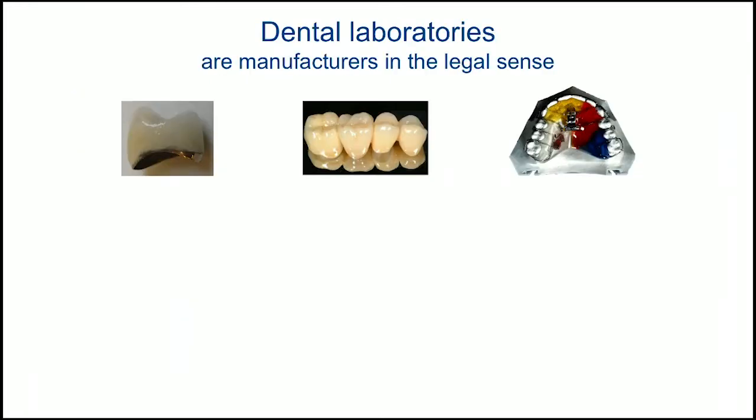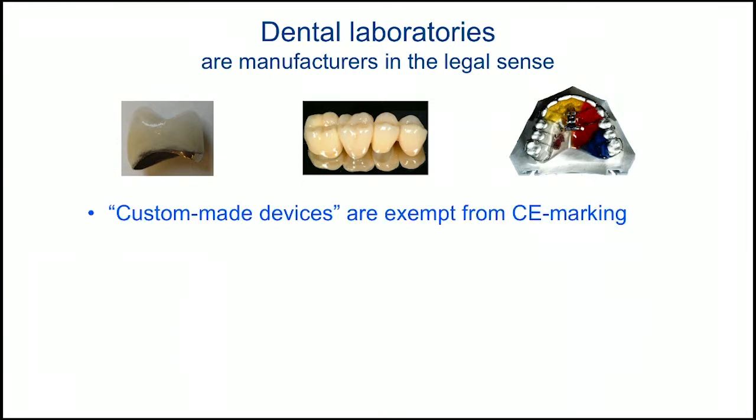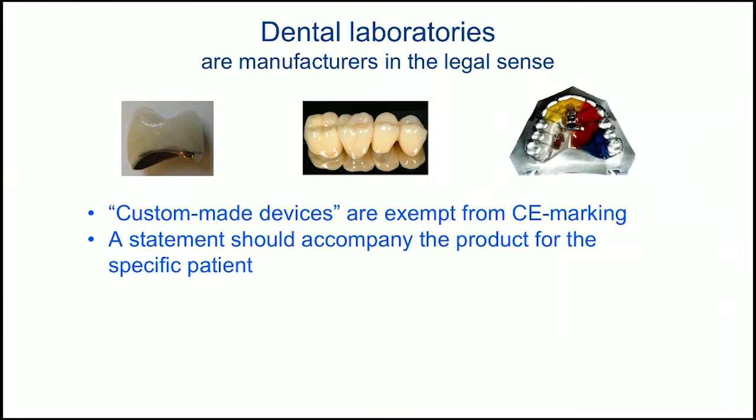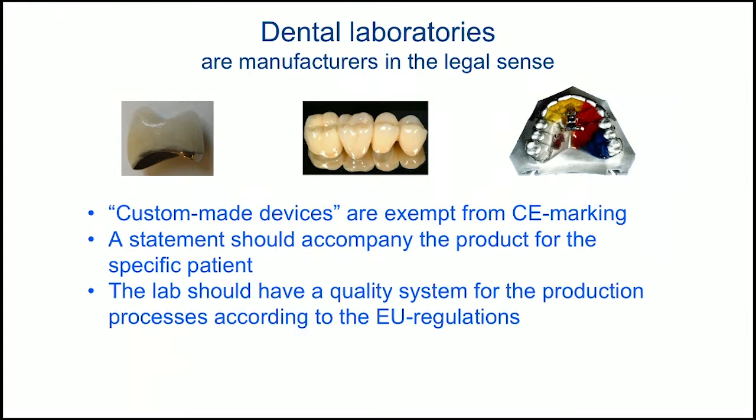Dental laboratories, a few words about those. They are said they are manufacturers in the legal sense. They make custom-made devices that are exempt from CE marking. But a statement should accompany the product for the specific patient. Also, the lab should have a quality system for the production processes according to the EU regulations.